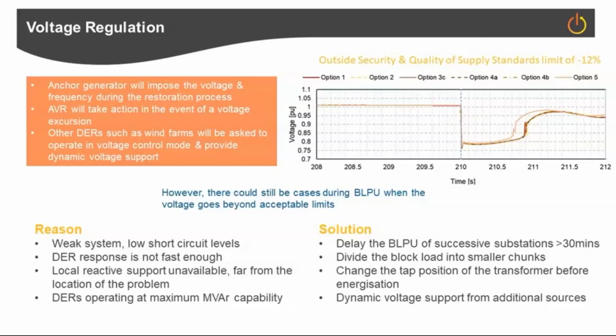Now, the rule of thumb we've used for our studies is the security and quality of supply standards, which are the operating standards that we apply over here in Great Britain. During a black start event, those security standards wouldn't necessarily apply, but if they were to apply, a voltage drop of 12% is all we'd be allowed to have. The example we showed you on this slide is a real example from one of our case studies. We're looking at about a 20% reduction in volts at the generator terminals. So there's a big issue there.